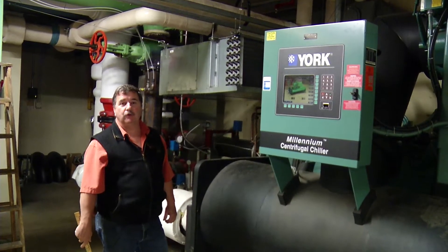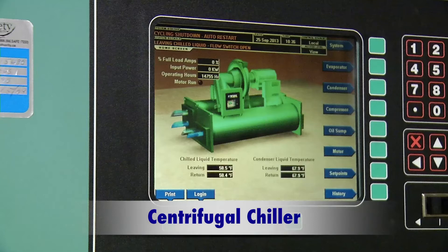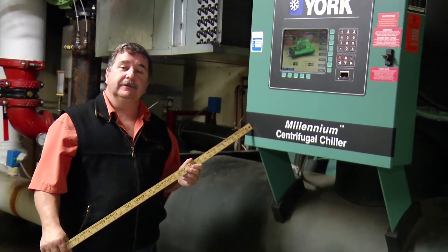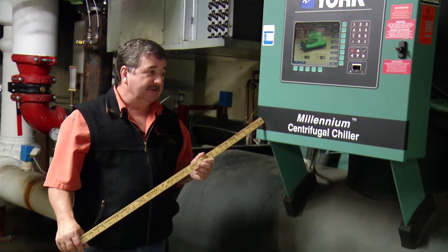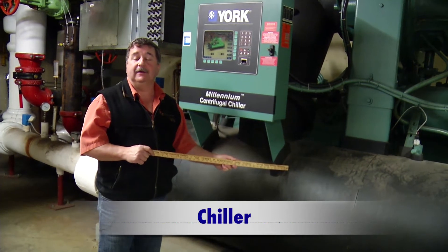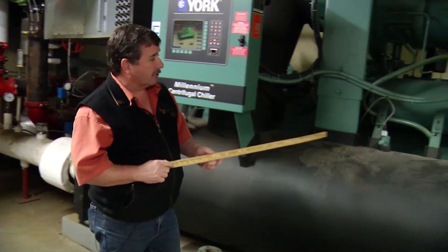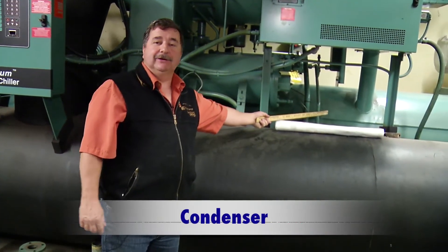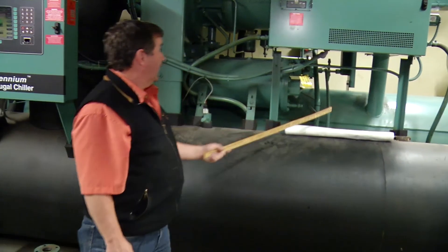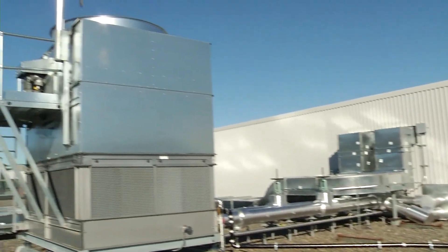We're in the mechanical room of building NE1 at BCIT, looking at the centrifugal chiller. This device is used to cool the complete building by cooling water. The components are similar to what we looked at before. We have what we call the chiller — basically a big barrel that works the same as the evaporator in the other unit. Across here we see the condenser, which is a water-cooled condenser, and the water from this goes up to the roof to be cooled at the cooling tower.